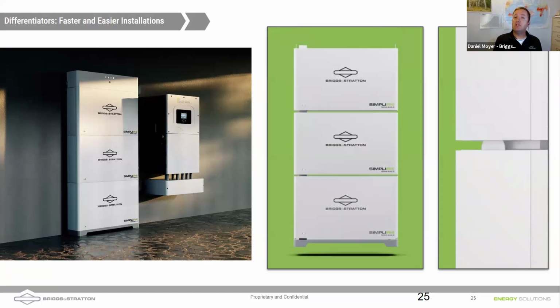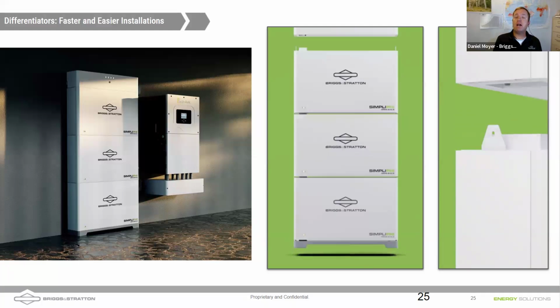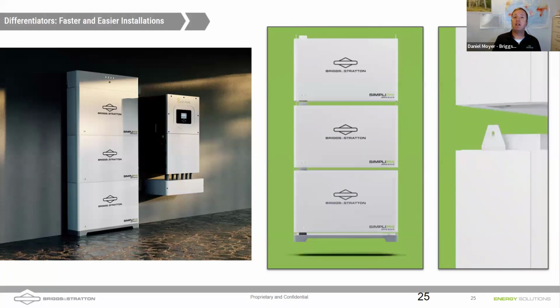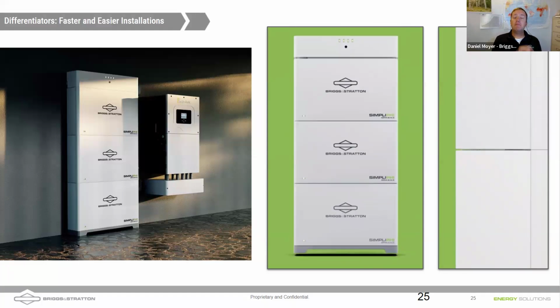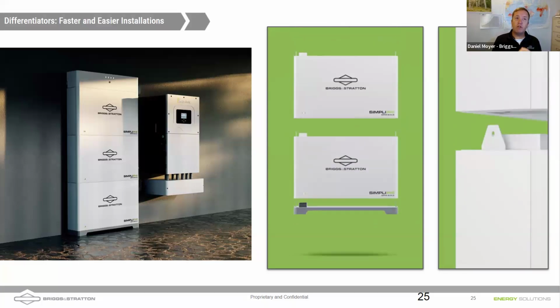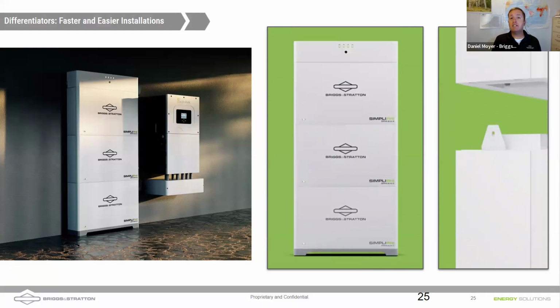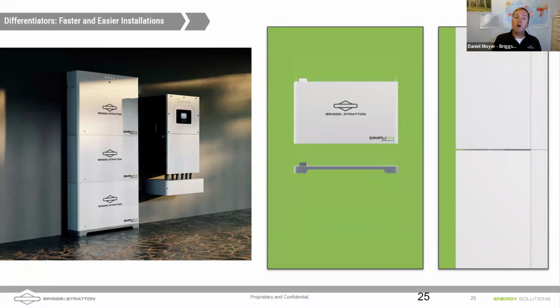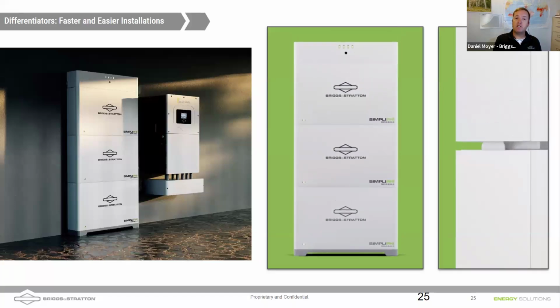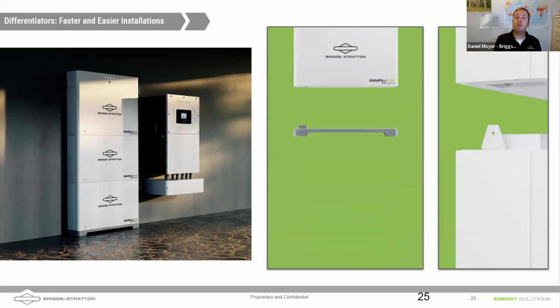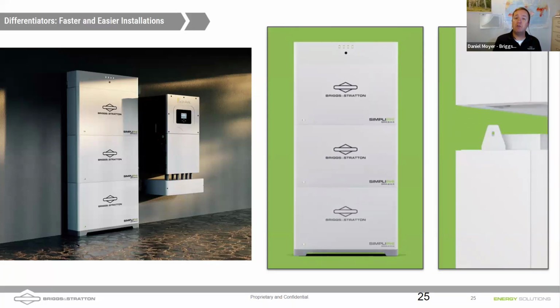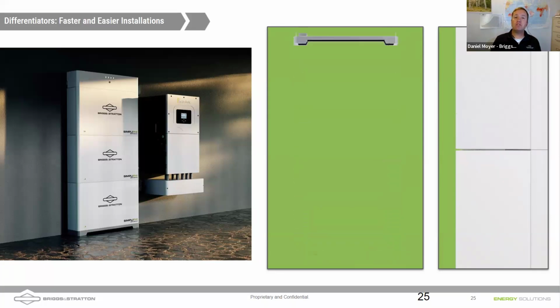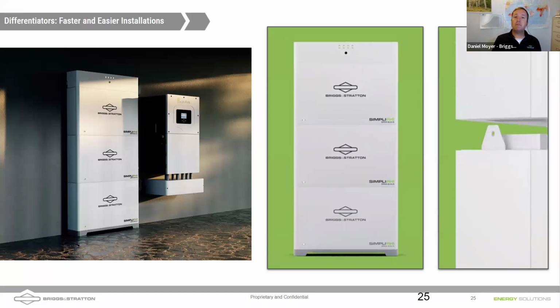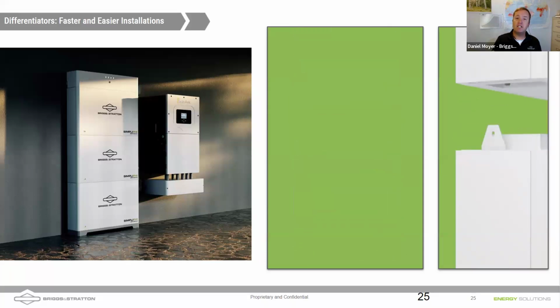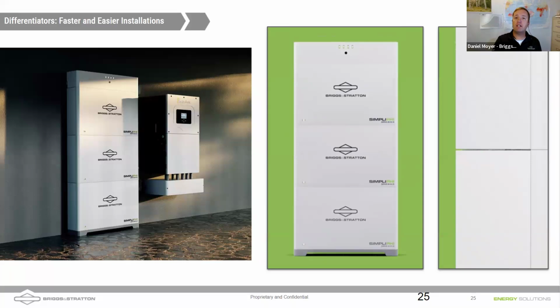What we've been able to do with some of this new generation of batteries is also have a very fast discharge rate, or C rate. With the Sol-Ark 15K in a grid, no-solar situation, it's capable of outputting 12 kilowatts. Our battery, this 6.6 with 3 battery stacks, is capable of providing 14,000 watts continuous discharge. So if that Sol-Ark is being called upon to start some loads, the battery connected to it will be able to discharge quickly enough to make sure the Sol-Ark isn't being starved of power from the battery.